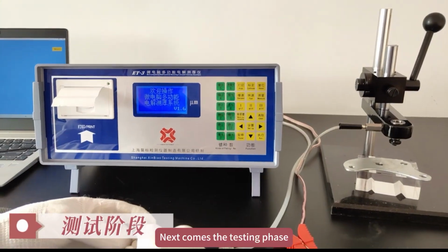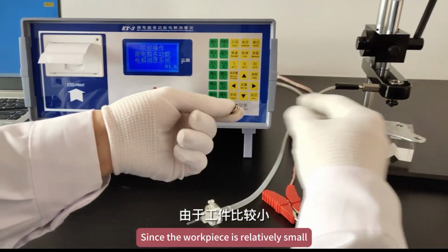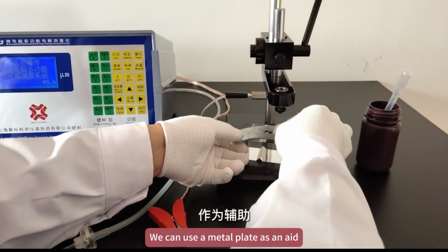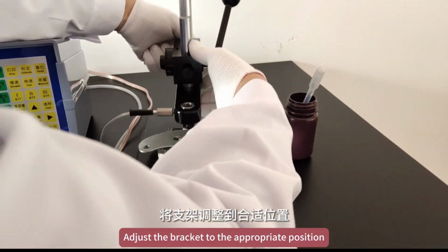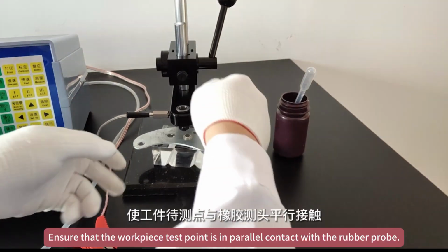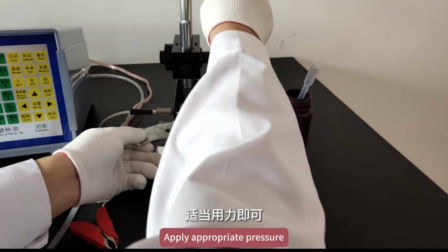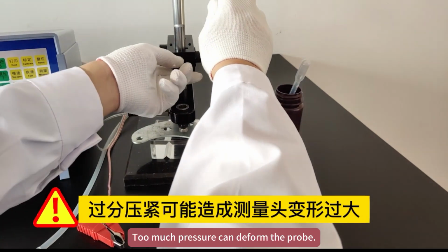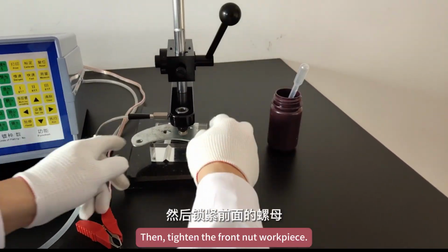Next comes the testing phase. Take the battery case as an example. Since the workpiece is relatively small, we can use a metal plate as an aid. Loosen the rear nut. Adjust the bracket to the appropriate position. Ensure that the workpiece test point is in parallel contact with the rubber probe. Apply appropriate pressure. Too much pressure can deform the probe. Introduce errors. Then, tighten the front nut.